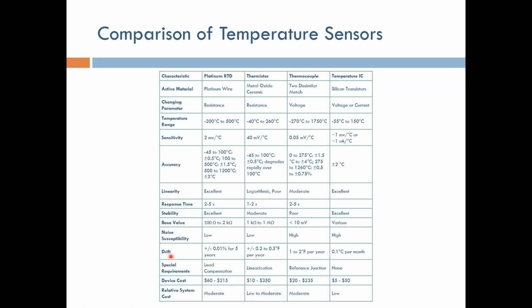For sensor drift, you're talking about variations. If you look at platinum RTD, for example, there are different types of RTD, but platinum is probably the best. As you see here, the drift is really very small, 0.01% over 5 years. That means after 5 years, it's just going to change either plus or minus a maximum of 0.01%.